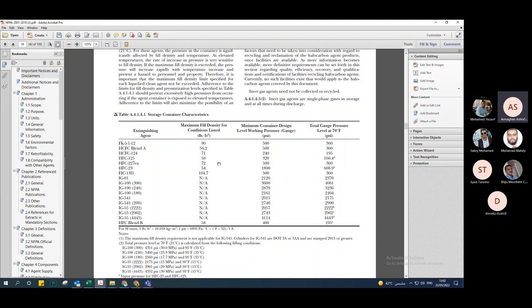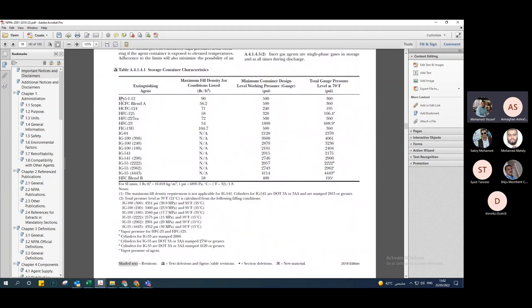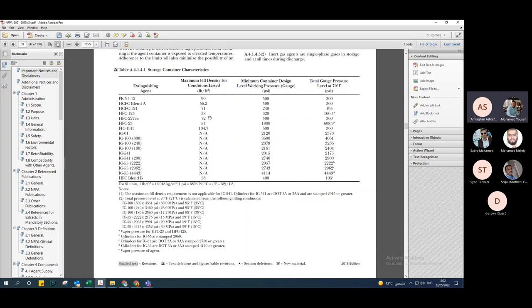Also from page 39, the maximum fill density for Novec system is 90 lb/ft³ and for FM200 it is 72 lb/ft³. From page 54, on piping system fittings for all halocarbon agents (Novec or FM200) at 360 PSI, the minimum acceptable fittings are: class 3000 threaded malleable iron or class 3000 ductile iron for all sizes; class 300 threaded malleable up to 3 inches; and groove-type fittings up to 6 inches.